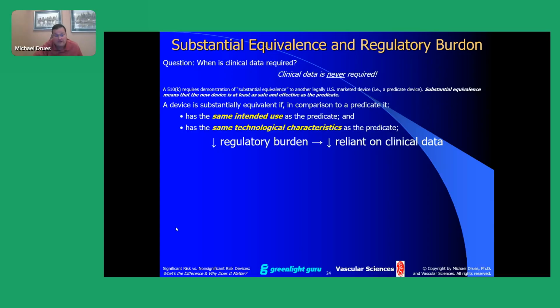So the regulation for a 510K says that a device is substantially equivalent if, in comparison to a predicate, it has the same intended use as the predicate and it has the same technological characteristics of the predicate. So what that means to us in terms of whether or not we need a clinical trial is it has a low regulatory burden. In other words, because it is so similar to the predicate, the likelihood that we're going to need clinical data to show its substantial equivalence is going to be relatively low. It's not going to be zero.